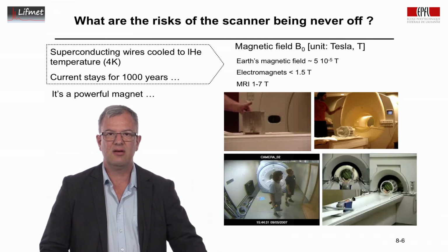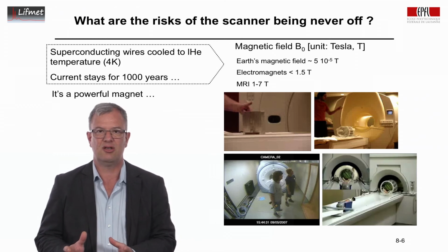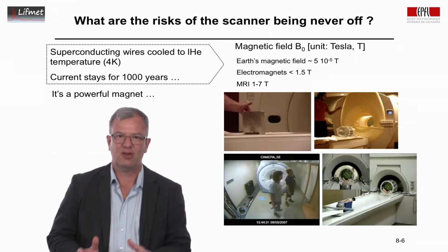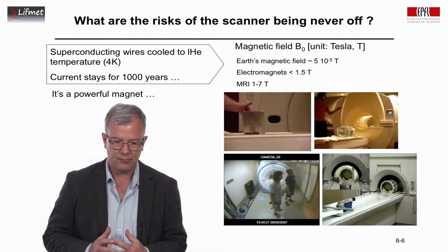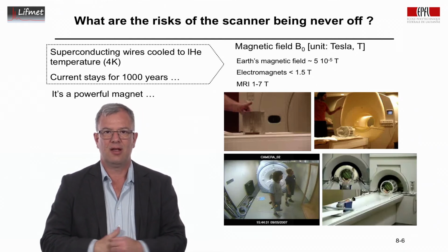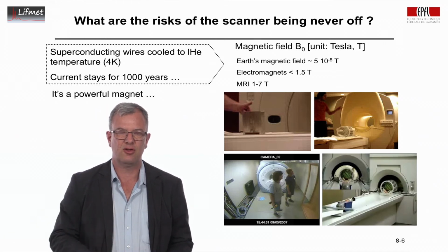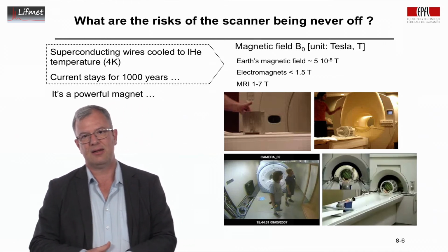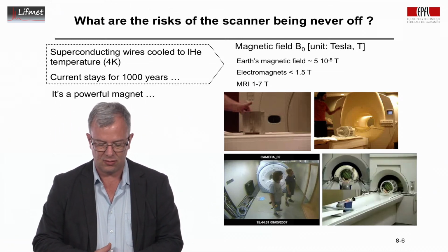The difficulty here is that medical professionals are trained to react to emergency situations, but they are not all trained to work and live around the magnet. So the first response is to help the patient. And so, yes, you grab the oxygen bottle, you run into the room, and the oxygen bottle is being attracted. That's the situation here.